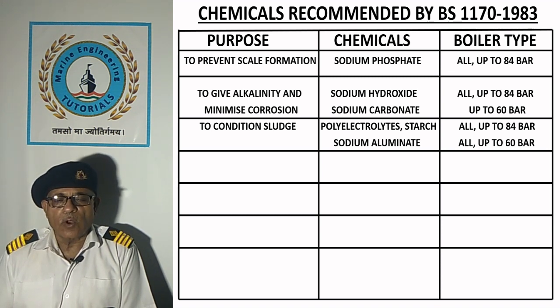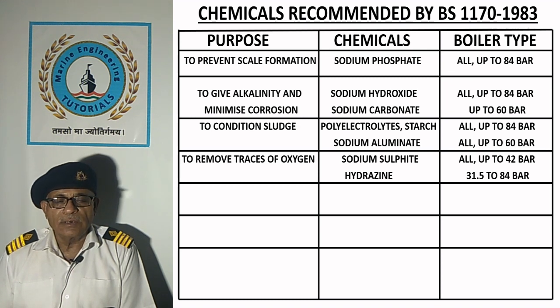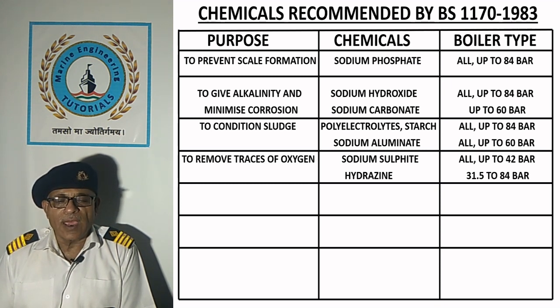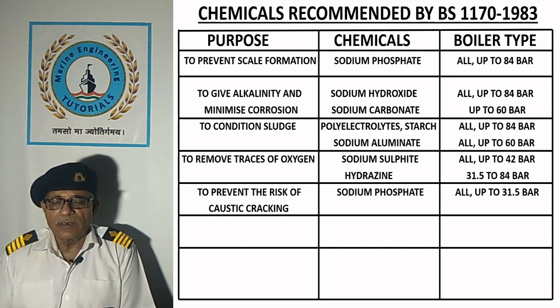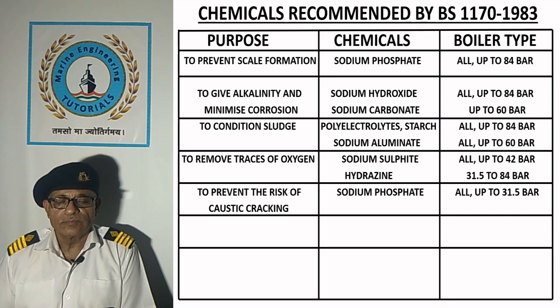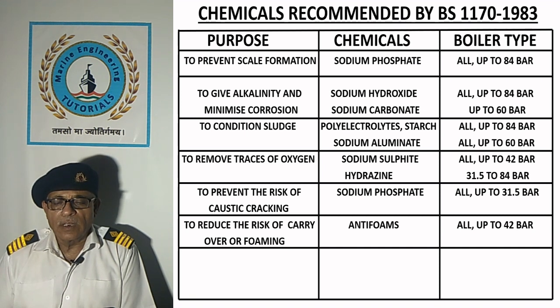Sodium aluminate is used for boilers up to 60 bar for sludge conditioning. To remove traces of oxygen, sodium sulfite is used for boilers up to 42 bar, and hydrazine for boilers from 31.5 to 84 bar — but mostly on motor ships where we have low-pressure boilers, we also use hydrazine. To prevent the risk of caustic cracking, sodium phosphate is used for all boilers up to 31.5 bar. To reduce the risk of carryover or foaming, antifoams are used for all boilers up to 42 bar.